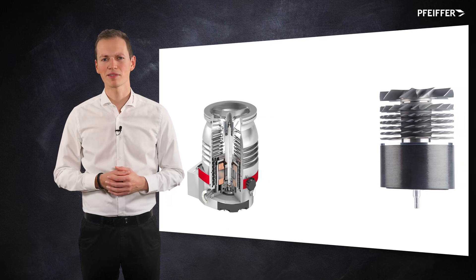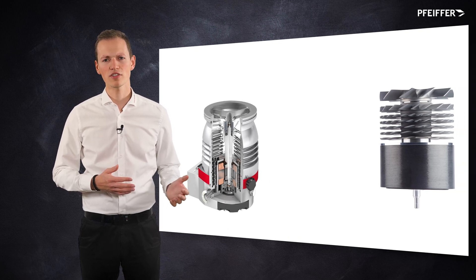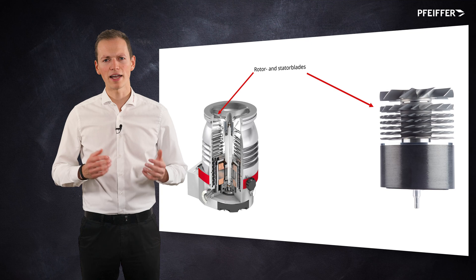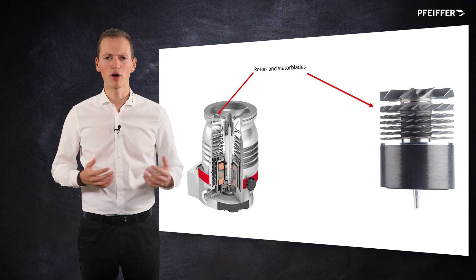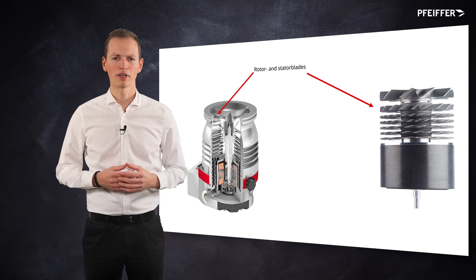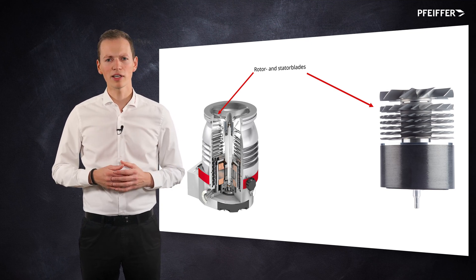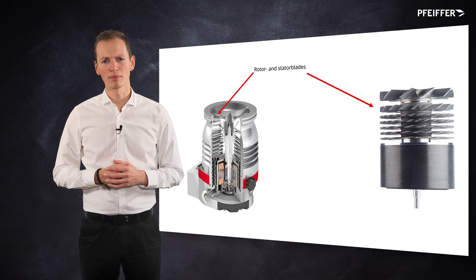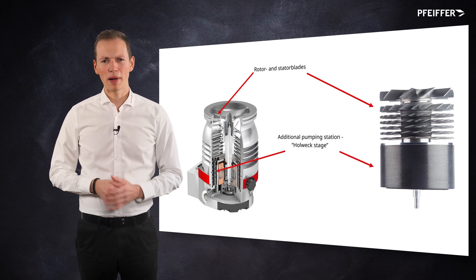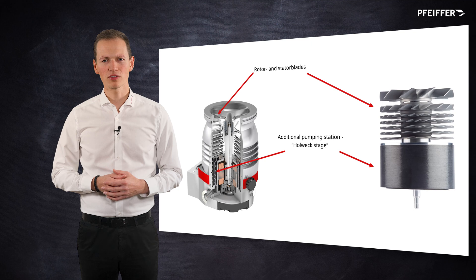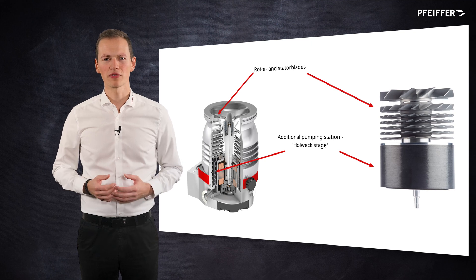In modern turbo pumps, there are several pumping principles combined. The so-called turbo pumping stages consisting of rotor and stator blades are common to all turbo pumps. They can be seen by looking into the high vacuum flange of the pump. To increase the compression ratio, additional pumping stages are often used downstream of the turbo stages.